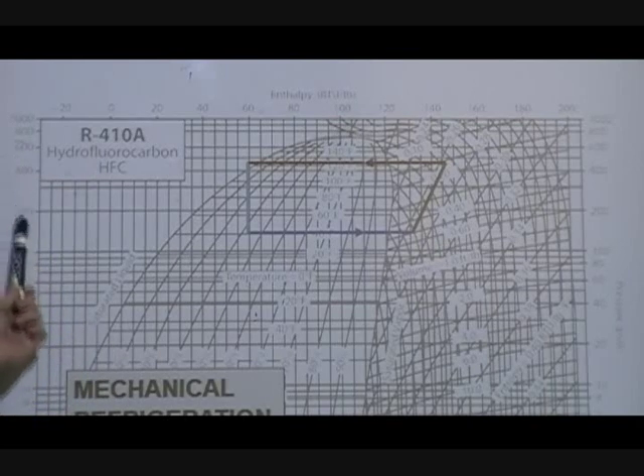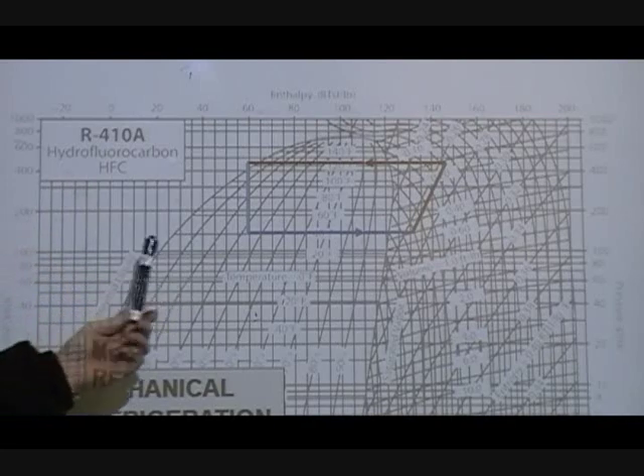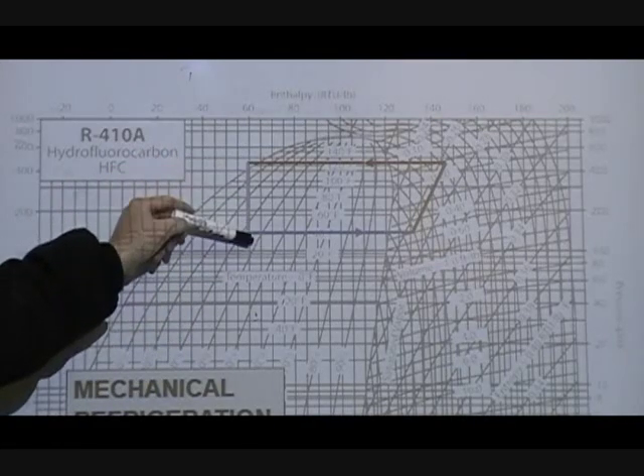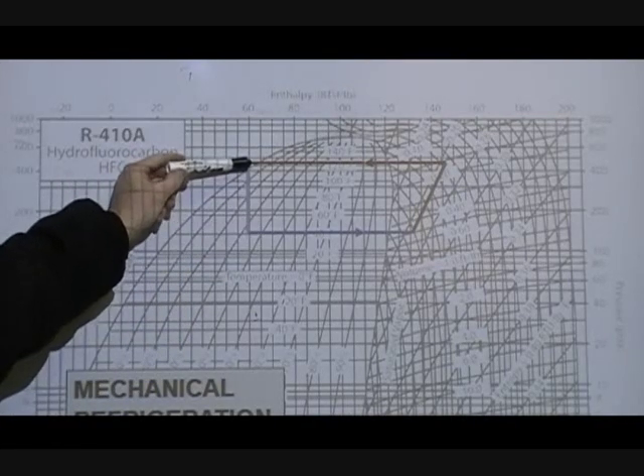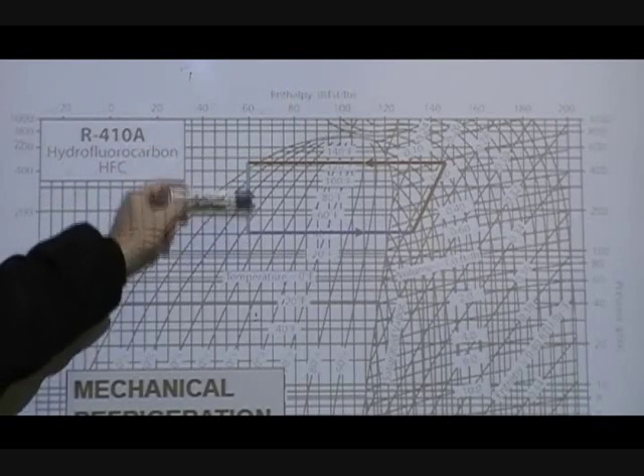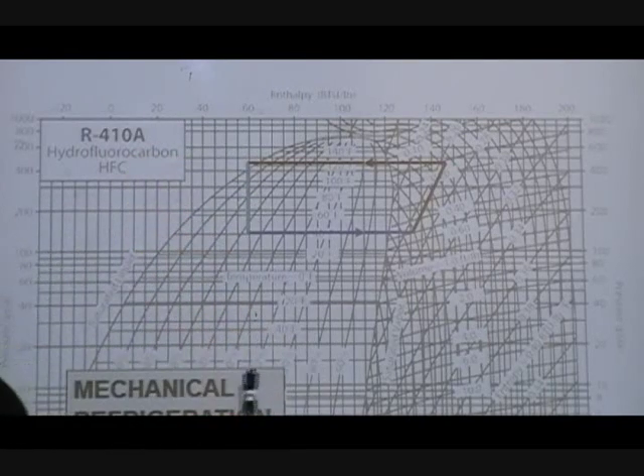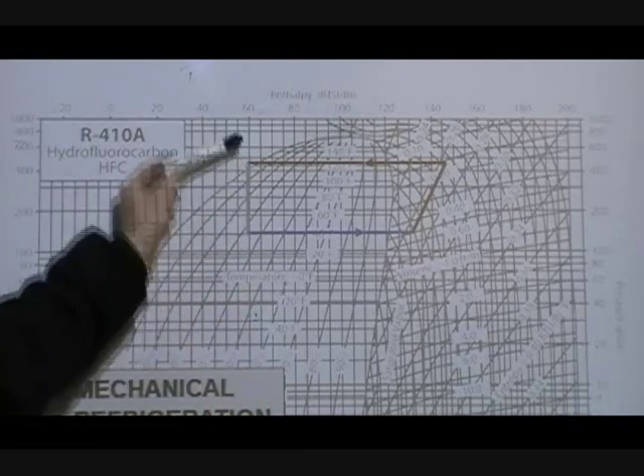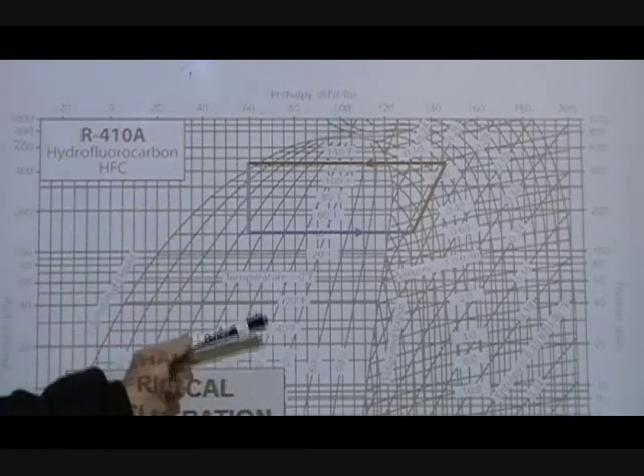So just keep in mind, your pressures are absolute. If you want gauge pressure, you subtract 15. Now, this is the phenomenon of the refrigerant going through the metering device. The pressure drops, the temperature drops, but no refrigeration effect occurs. So it all happens on a vertical line.